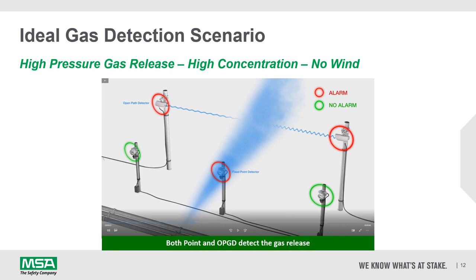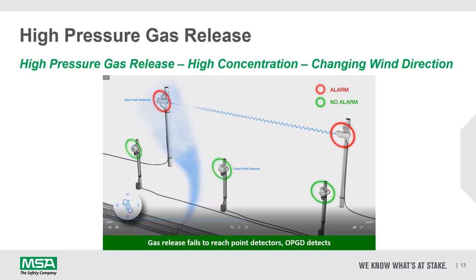Over the next few slides we're going to look at some different gas release scenarios and how they relate to both point and open path detection. Here's the ideal scenario. A gas release from a flange in the bottom left hand corner of the image is sending a high pressure gas release over a point detector or cutting an open path beam, both of which detect the gas release. Here the same high pressure gas release is being affected by a change in wind direction, and as a result is not being detected by the point detectors. However, the gas release is being seen by the open path device. Therefore, an open path device has a better chance of seeing a gas release in environments of changing wind direction.